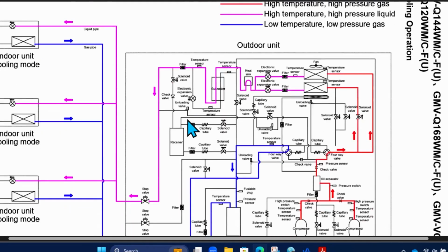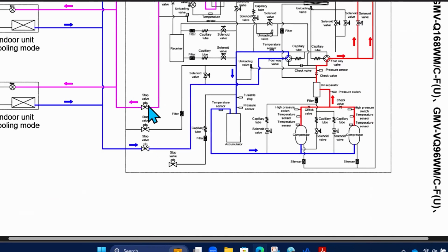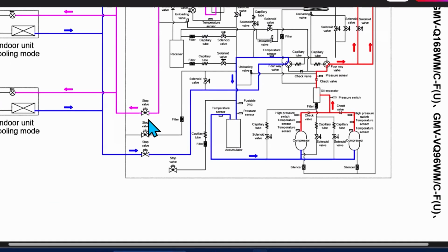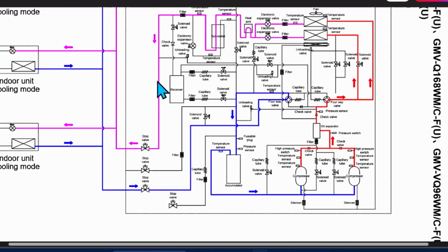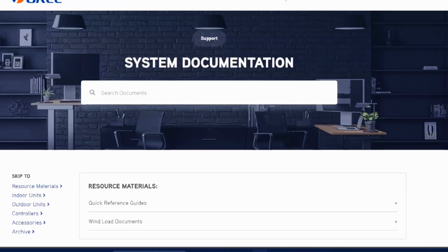Just an FYI, the piping sequence as far as the valves go here, they're not sequential to the way the pipes are in the unit. So be very careful that we connect to the right two pipes. I don't want to get in depth today on refrigerant flow for heat recovery versus heat pump, that's more of a technical training, and I don't feel like we have the time for that today.